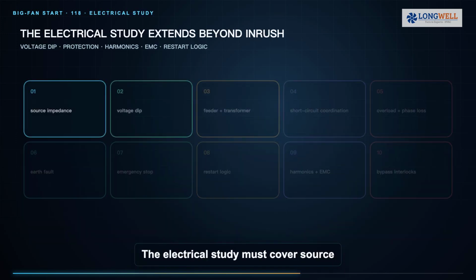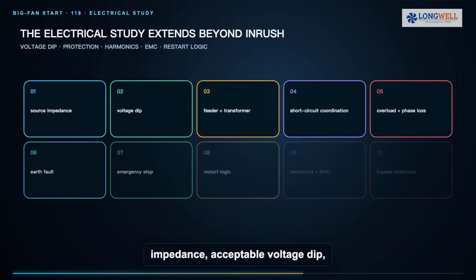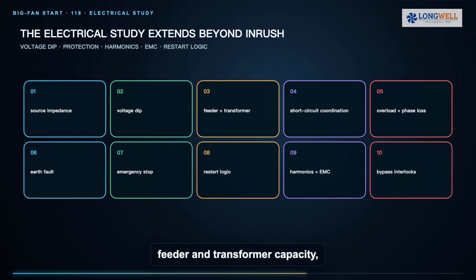The electrical study must cover source impedance, acceptable voltage dip, feeder and transformer capacity, short circuit coordination, overload behavior, phase loss, earth fault, emergency stopping, and restart logic. A VFD adds rectifier harmonics and high-frequency output considerations. A soft starter adds semiconductor thermal duty and bypass coordination. DOL still requires engineered protection and interlocks.